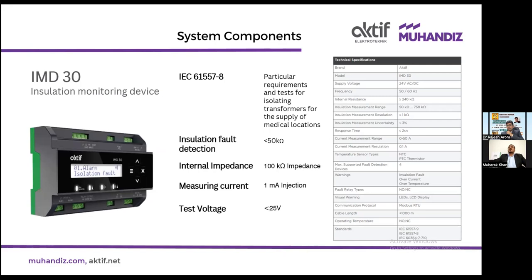There are some technical requirements, like internal impedance should not be more than 100 kilo ohm, measuring current 1 milliampere maximum, which it should not cross, and test voltage less than 25 volts. So actually the device is complying much better than the standard.